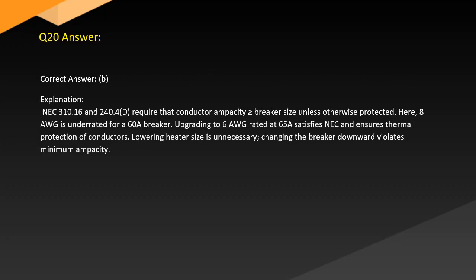Answer. Correct answer: B. Explanation. NEC 310.16 and 240.4(D) require that conductor ampacity ≥ breaker size unless otherwise protected. 8 AWG is underrated for a 60-amp breaker. Upgrading to 6 AWG rated at 65 amps satisfies the NEC and ensures thermal protection of the conductors. Lowering heater size is unnecessary. Changing the breaker downward violates minimum ampacity.